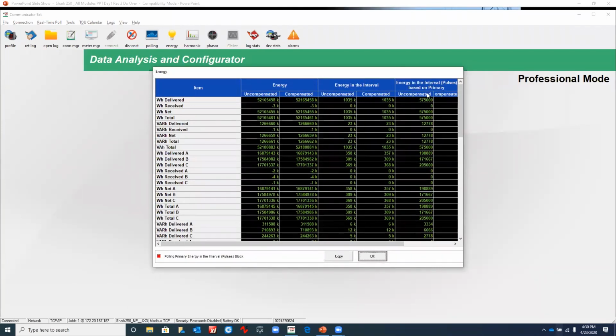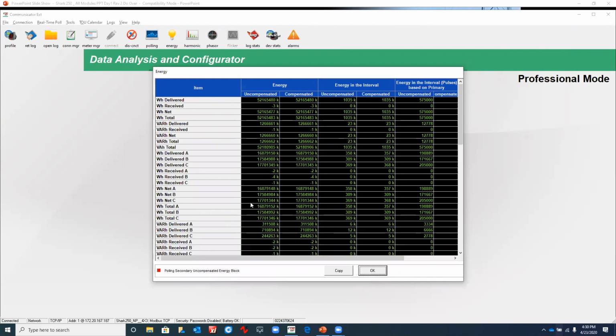Energy in interval pulses is another way of the meter recording pulses internally. It has an internal recorder where it stores this information, and you'll see it recorded in pulse value, not in an energy value. So everything here pretty much replicates similar information that we saw previously, except these are all energy values. These are not instantaneous values. It's the energy for an interval period.